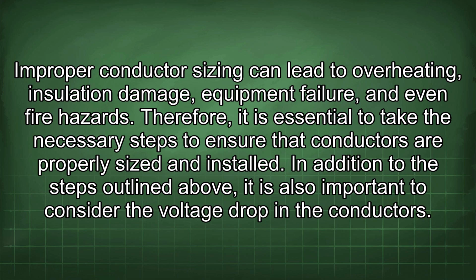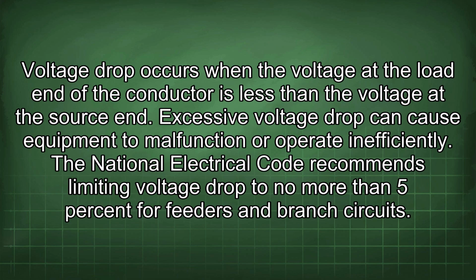In addition to the steps outlined above, it is also important to consider the voltage drop in the conductors. Voltage drop occurs when the voltage at the load end of the conductor is less than the voltage at the source end. Excessive voltage drop can cause equipment to malfunction or operate inefficiently. The National Electrical Code recommends limiting voltage drop to no more than 5% for feeders and branch circuits.